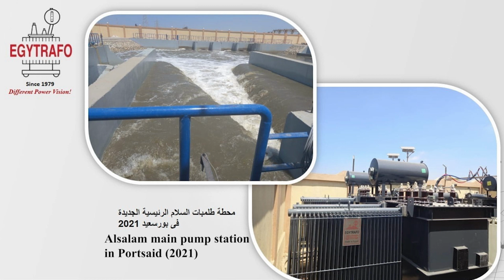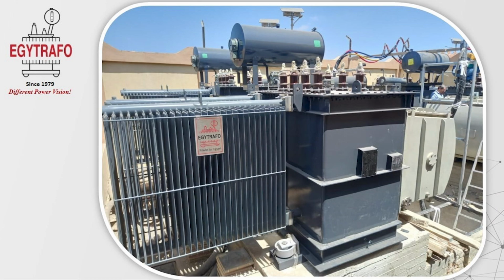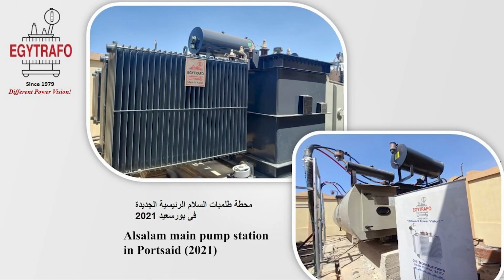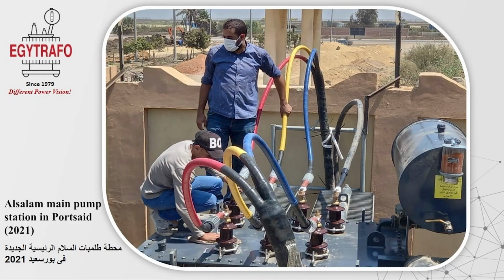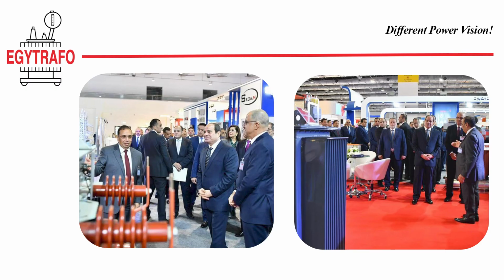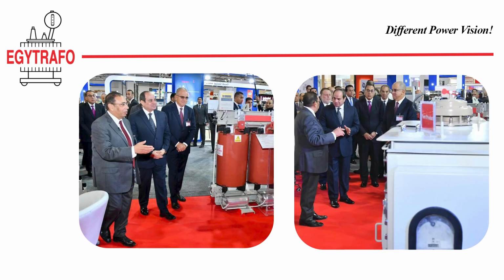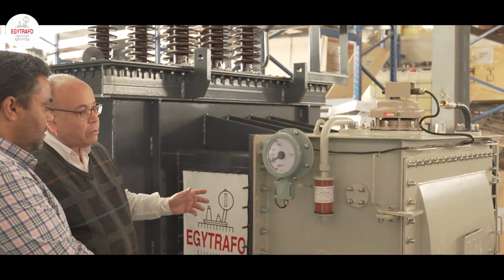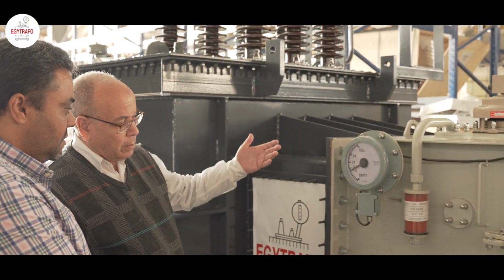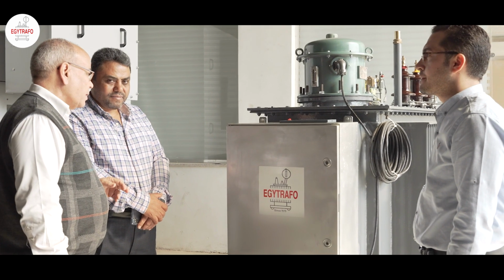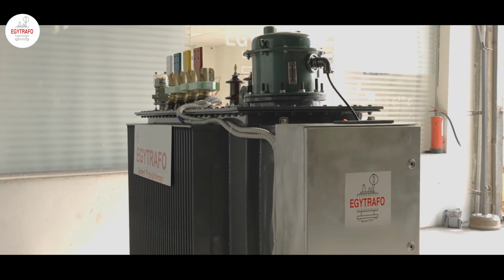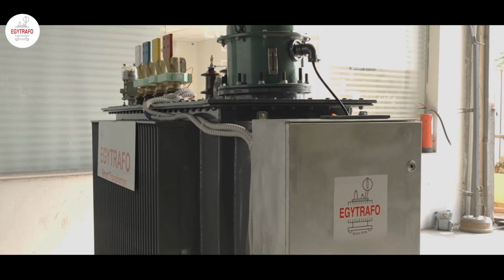3-phase automatic voltage regulator, to overcome the reduction of voltage at far ends of the line source, rating up to 33 kV 600 amps, automatic or manual tap changing equipment. Advantages: less copper losses, small size as the 3 phases are in one tank, less weight, smooth variation of voltage, the capability of measuring voltage at any tap, having a tap position indicator. Smart transformers, distribution transformer according to IEC standard, on-load tap changer, control box containing controller with AVR, RTU.